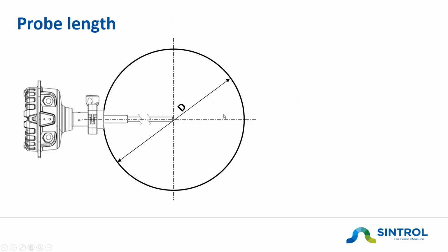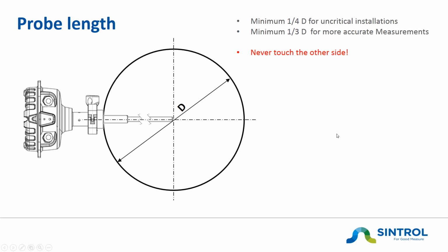Probe length. For uncritical installations, we recommend the probe to be about 1/4 of the duct, and for more accurate measurements, we recommend a minimum of 1/3 of the duct. However, make sure that your probe never touches the other side of the duct, because that would create a shortcut between the probe and the metal duct. And that would completely distort all our measurements.